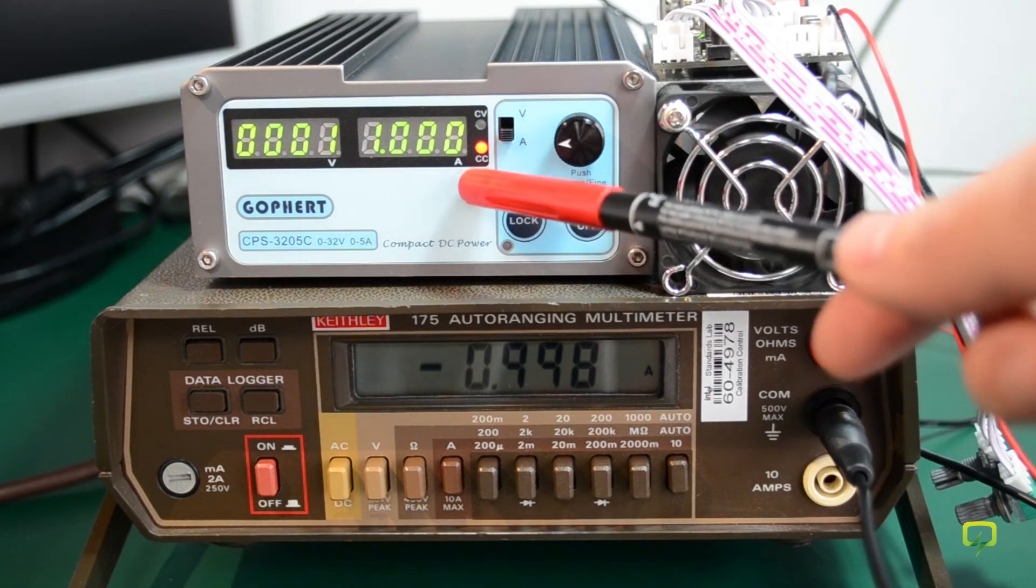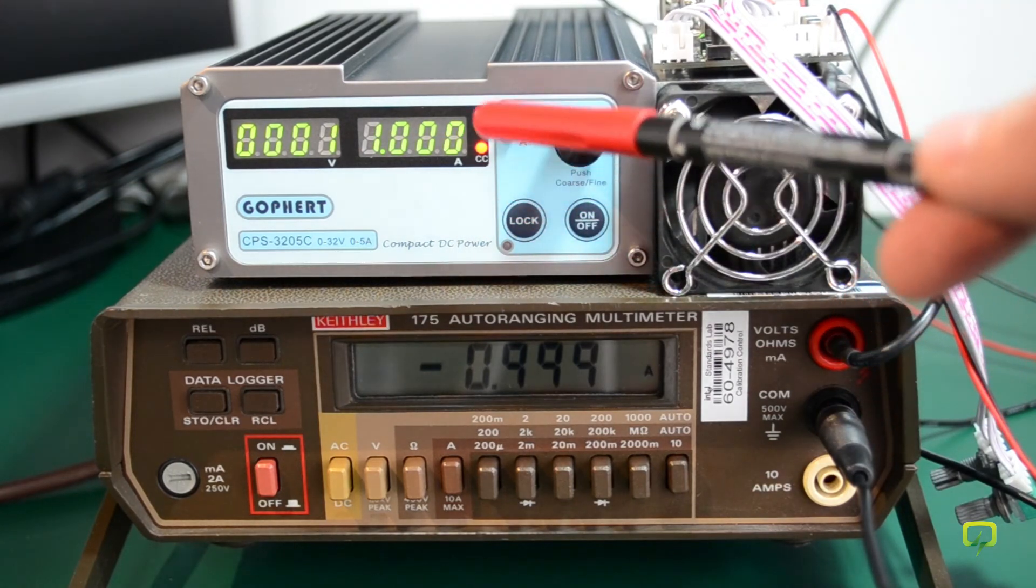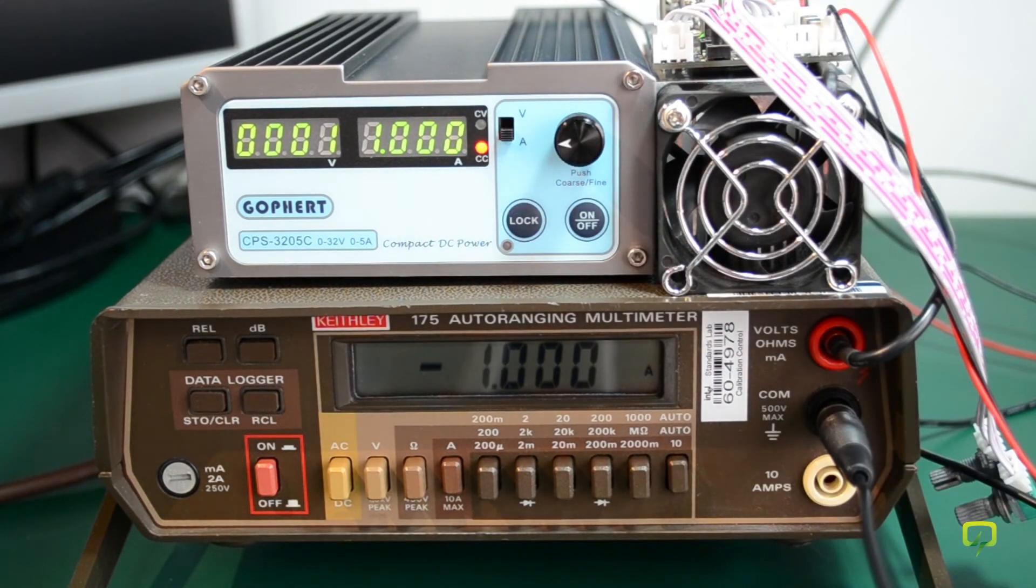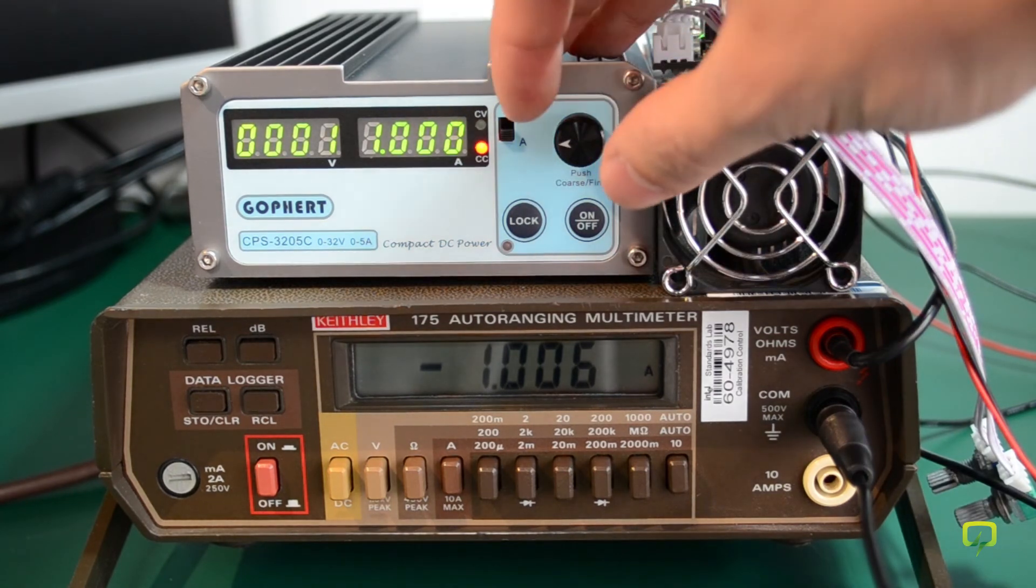The power supply is operating in constant current mode, and it is in the 1 amp calibration range. Now you have to adjust the output of the power supply to set the constant current to 1.000 amps. So let's try to do that.